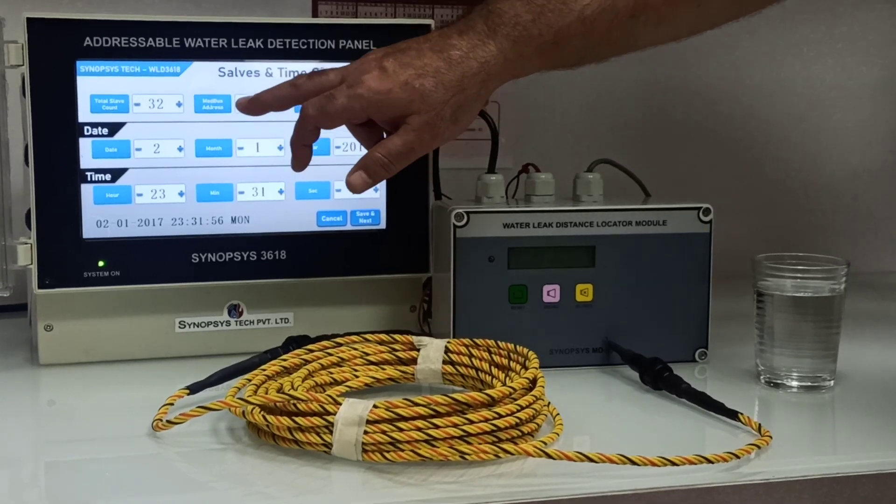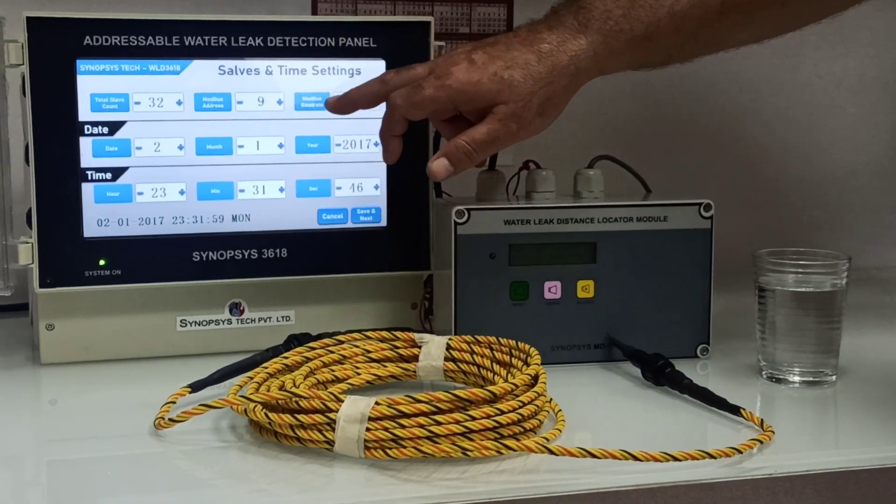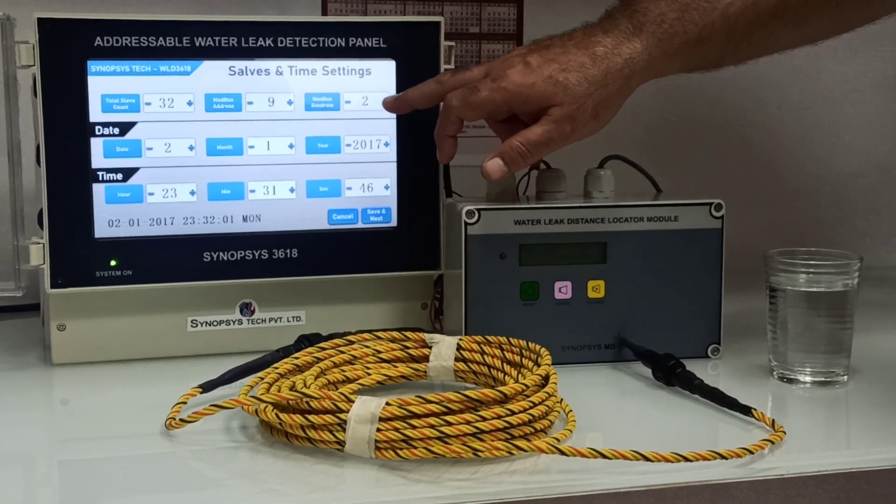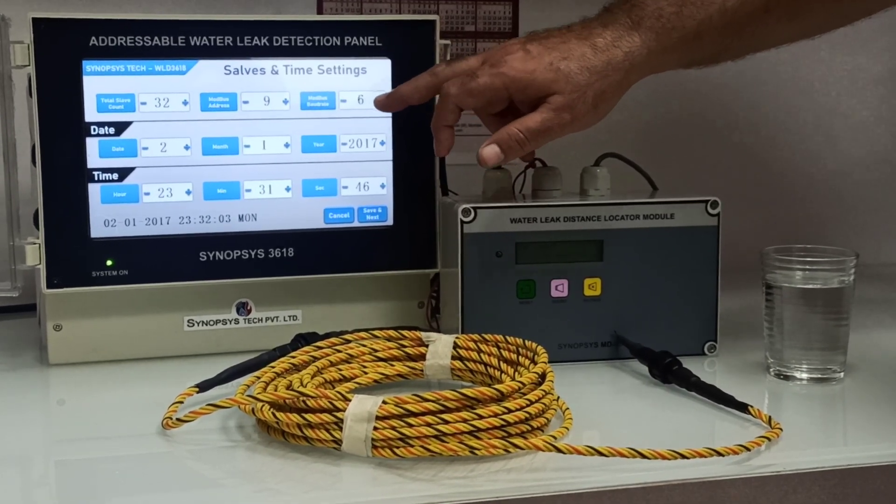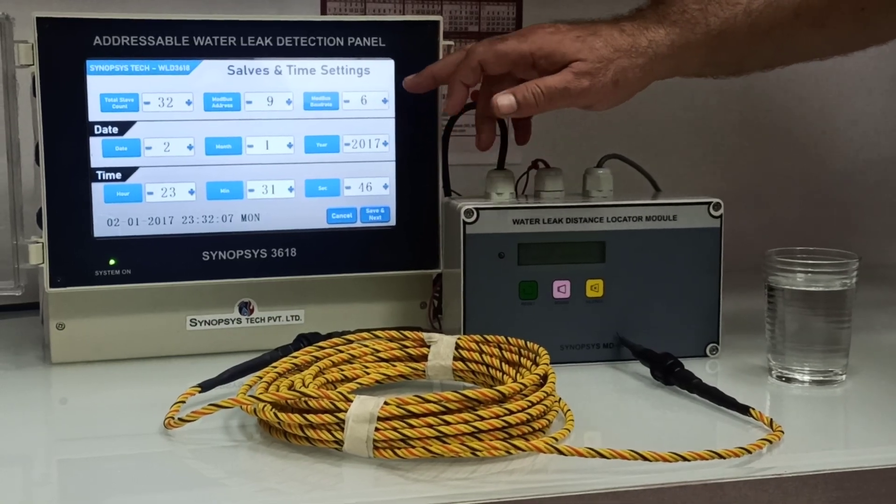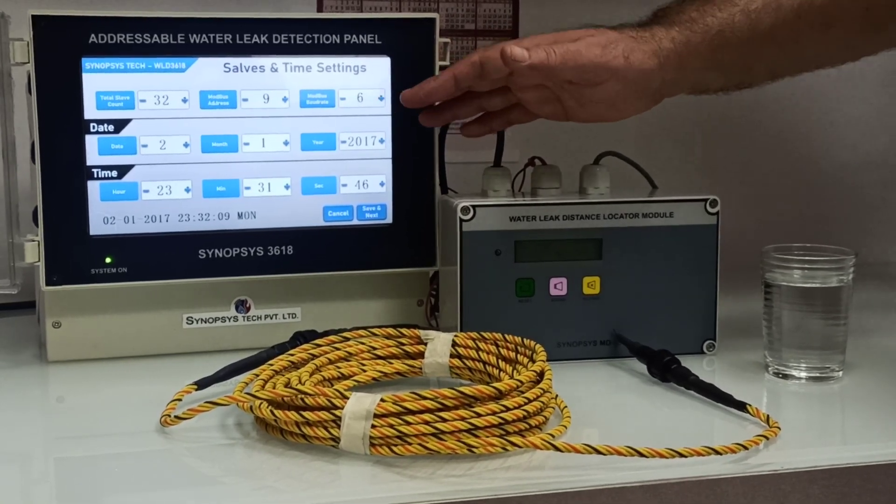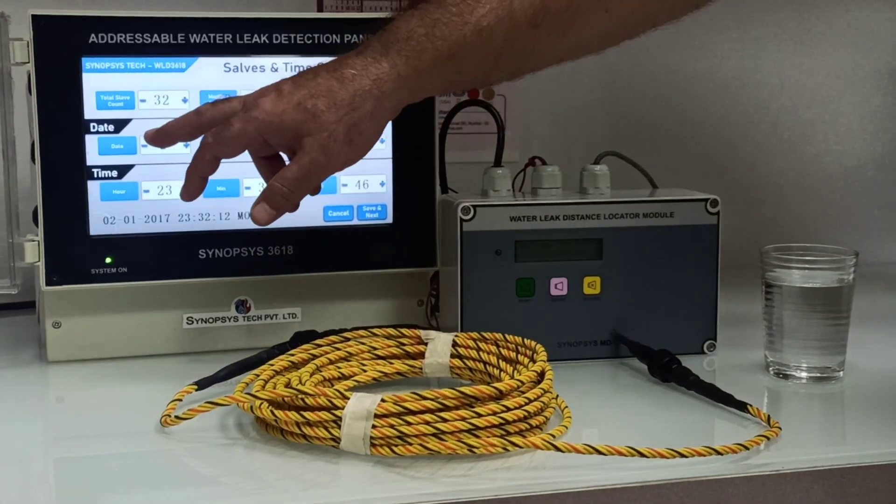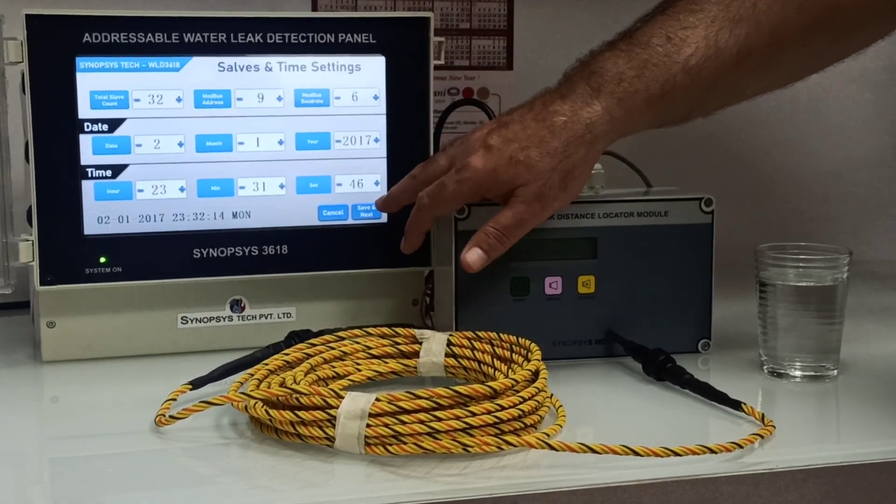Then we have Modbus address which you can change, then we have Modbus baud rate. This is a feature which normally others don't have - we can have six types of baud rates. According to the BMS system we can change the baud rates. We have date and time which can be changed.